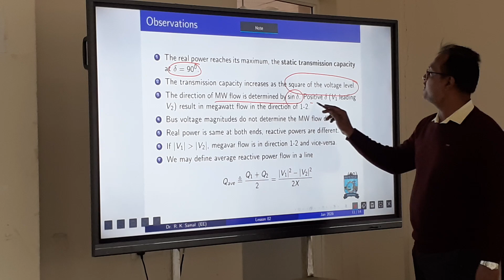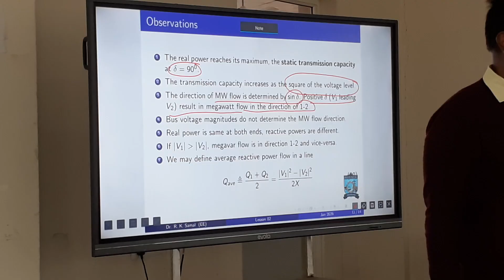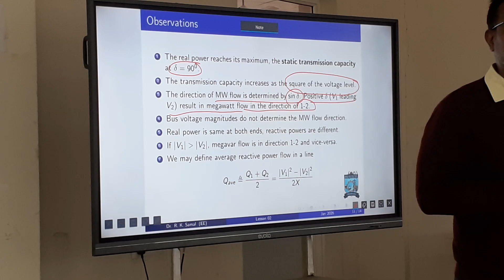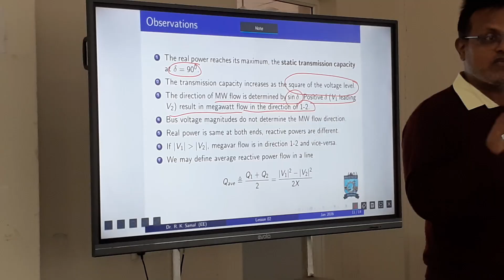Load angle is again directly related to what? The prime mover. What is the phase difference or relative position of the prime mover, which is rotating, with respect to the rotating magnetic field? That is delta. So it eventually depends on the prime mover, the real power input. Delta depends on the real power input, and therefore the power flow in the transmission line is dependent on the difference of the voltage angles, not the voltage magnitude. Always remember, voltage is important to maintain a steady profile so that voltage collapse does not occur, but actual power flow can occur only when a delta difference is there.